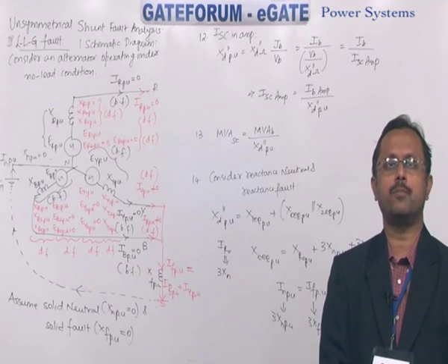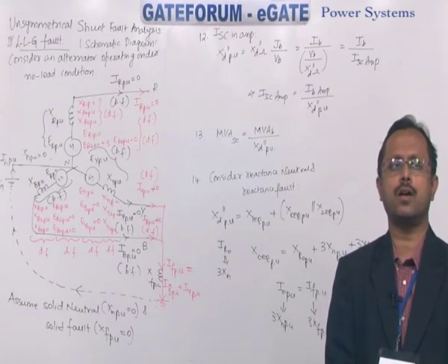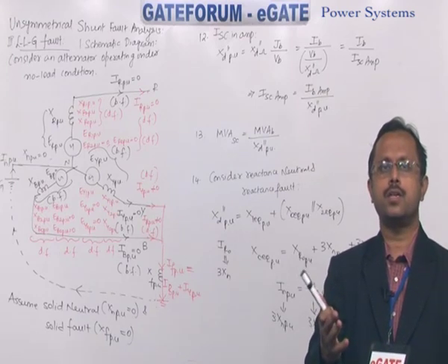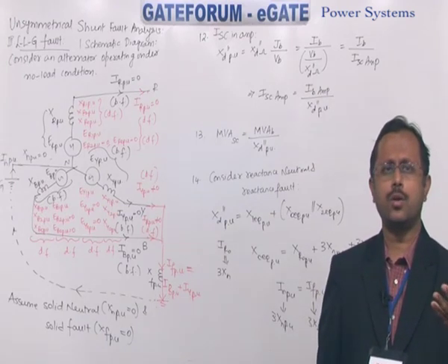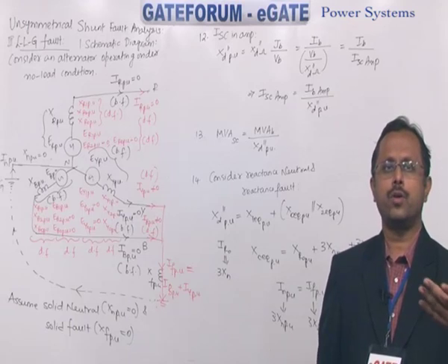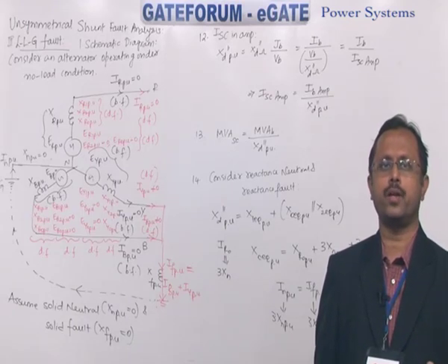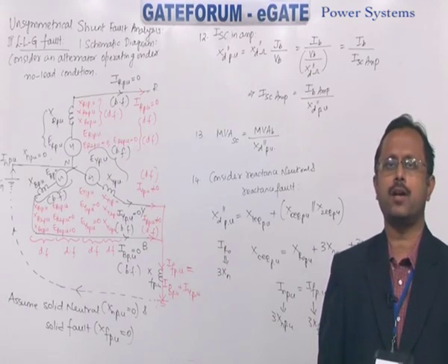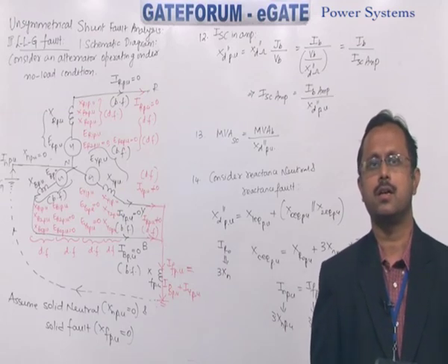Next question is by Tanmay. How can we analyze fault current if neutral is not grounded? If neutral is not grounded, zero sequence current IR0 does not flow. So you don't have X0 equivalent per unit. Like in LL fault or in triple L fault, we can come across such conditions.